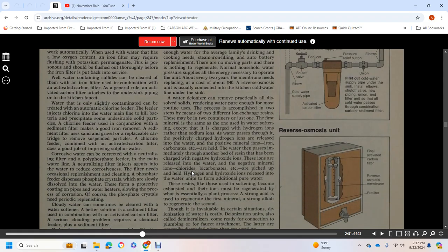A water deionizer removes practically all dissolved solids, leaving the water pure enough for the most routine use. The process is accomplished in two steps with two different ion exchange resins. They may be in two containers or just one. The first resin is the same as the one used in the water softener, except that it is charged with hydrogen ions rather than sodium ions.